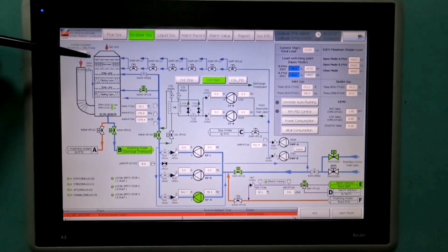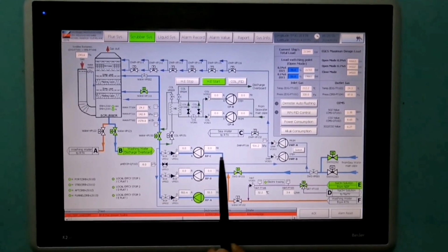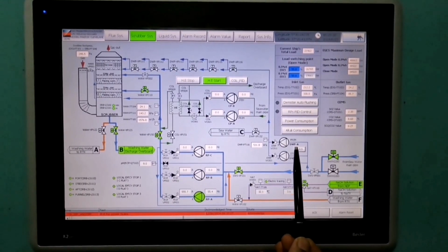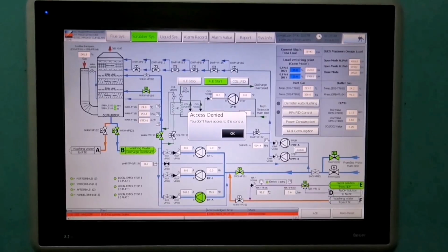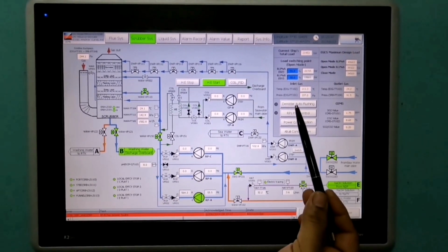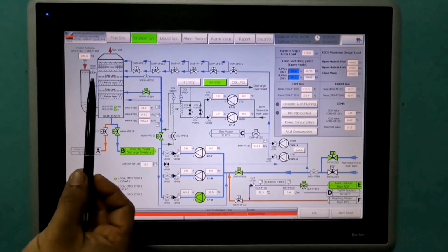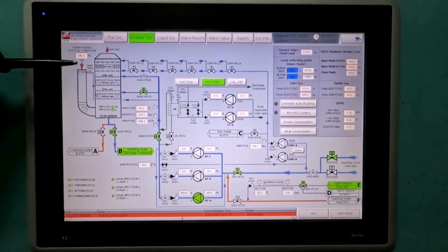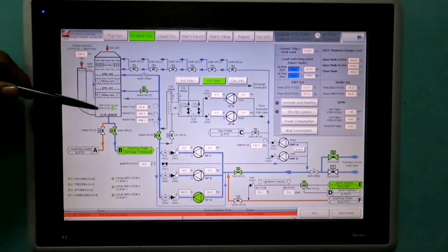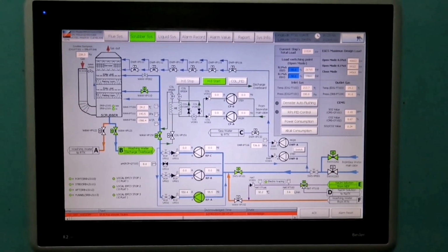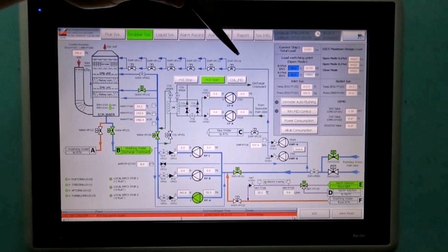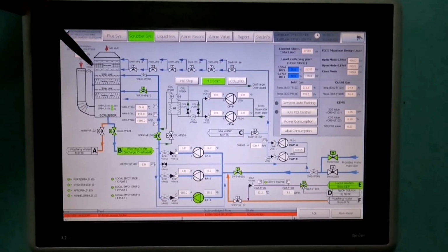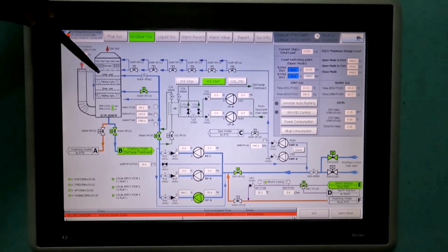This demister on top also has nozzles, but there is a separate pump for that one, the DWP pump. This pump has a setting for how many hours it should flush. These settings you can change as per the duration. You can change how many hours you want to flush this demister, because in the end the exhaust gas is passing through this demister and going out. So one by one these valves will open for 1 minute as per the setting, and then this will spray water on the demister, and on these nozzles, if there are any deposits, they will get washed away.